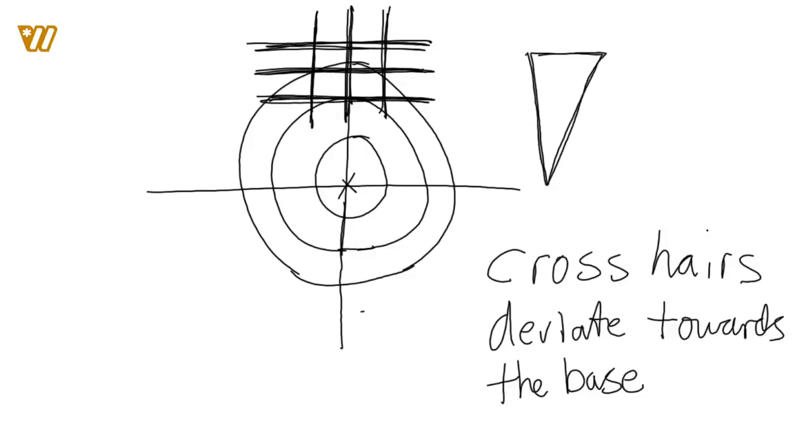All right, let's clear the whiteboard and work one more example. Let's dive into example 5.2. When using a lensometer, the sphere power is found to be -3 diopters and the axis is 125. The power wheel is then rotated in the minus direction until reaching a power of -4 diopters, at which point the cylinder lenses become clear. What is the power of the lens? Go ahead and take a second, pause the video, work out the problem, and then we'll work it together here on the whiteboard.